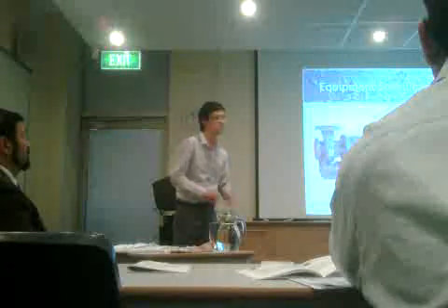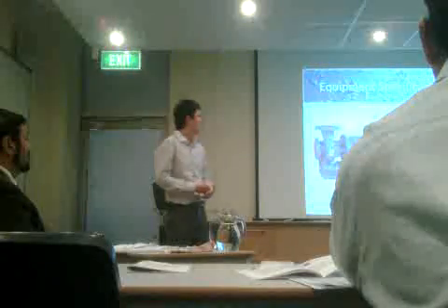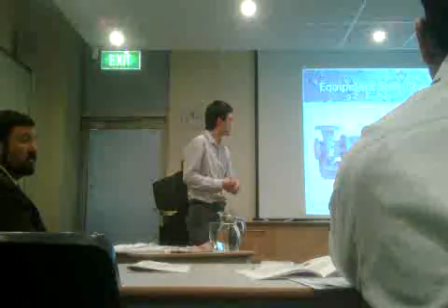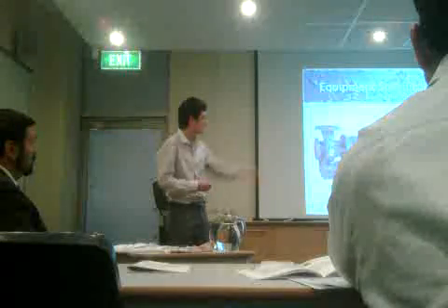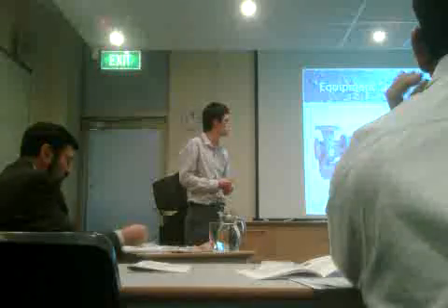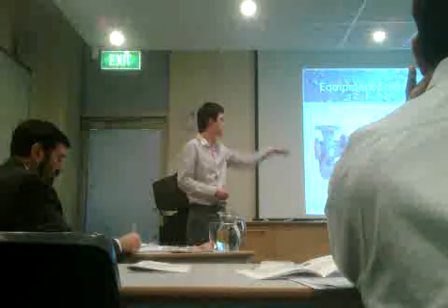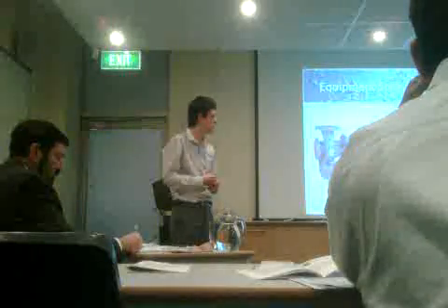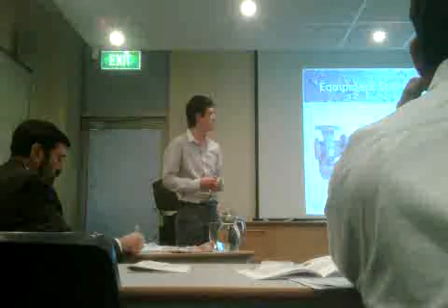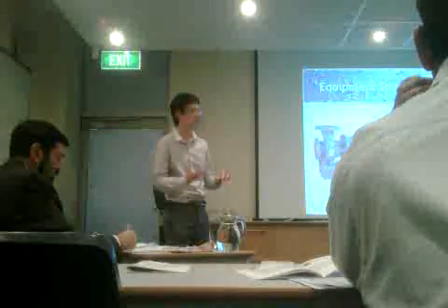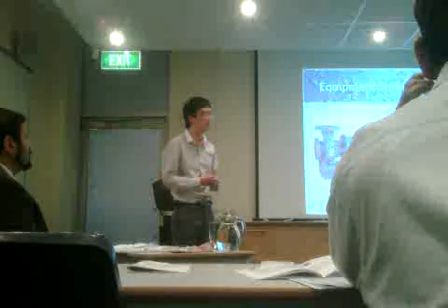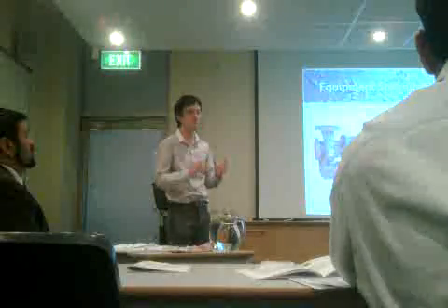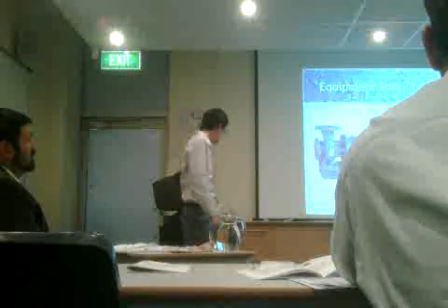The next equipment is the centrifugal pump. Important things to notice here are the last three pieces of information: the NPSHR and NPSHA. NPSH stands for net positive suction head. A here stands for available, and R here stands for required. NPSHA must be greater than NPSHR at all times in order to prevent cavitation from happening.